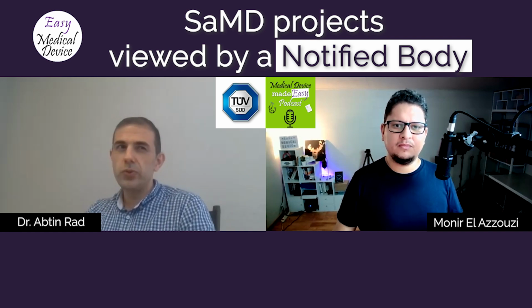Yes, actually, there are. As I told you, the MDCG guidance is quite good, very good, actually, but doesn't really tell you how to be compliant. So there are no technical requirements there. And fortunately, we do have standards. The first one has been published in February this year, if I'm not wrong. This is the IEC TR 60601-4-5. It's a technical report, unfortunately. However, it's really a good standard. I tell you why. Usually the 60601 series of standards are only for hardware devices, but this also includes medical device software.